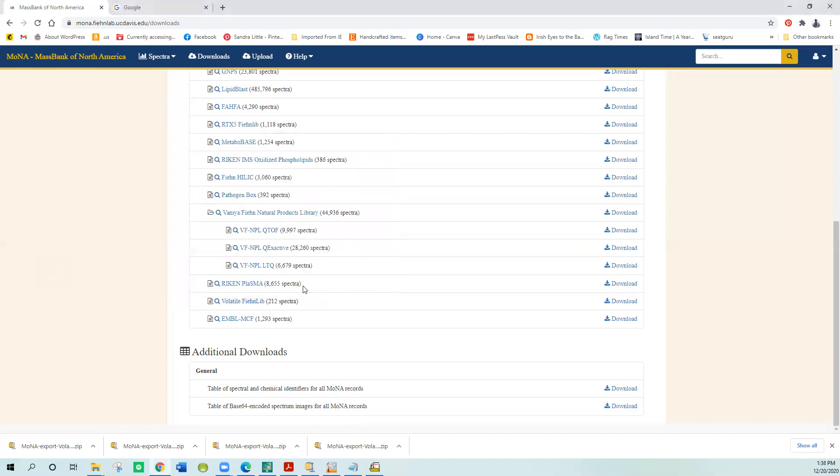Now if you go to your NIST search and look for that and set it up as a library, it will be there. You just add it to your list and search. It's not real difficult to do, but you just have to get everything down to the right place. You have to get it in the right folder, you have to unzip it, and then you have to make sure it's in the right place when you put it back. It's better if you put the folder that has 45 to 55 files, the indices it created, in the NIST 20 MS search folder so it can be used by the NIST search program.